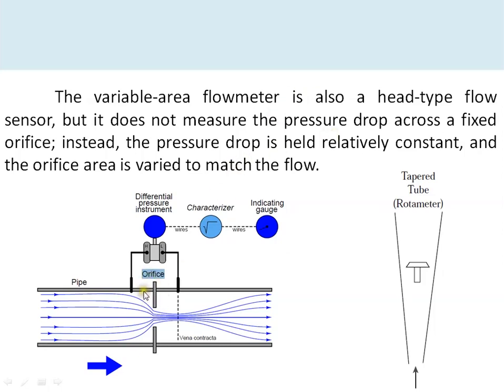The variable area flow meter is also a head type of flow sensor. An orifice is also a head type flow sensor, but in an orifice the restriction is fixed, and an increase in flow rate causes an increase in pressure drop, which is measured by a differential pressure transmitter to give the flow rate. In a rotameter, with an increase in flow rate, the area changes and the pressure drop across the float always remains constant — only the area changes.